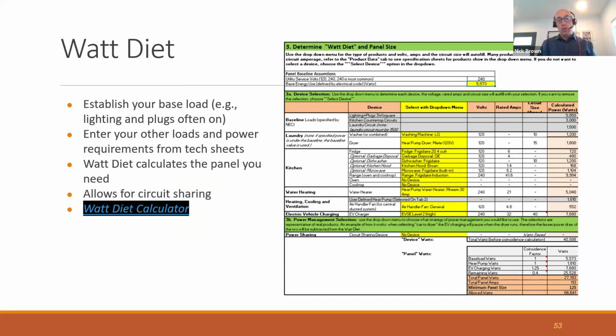Watt Diet's a useful tool in this sense. It is a spreadsheet application available through the link, and we're going to send out the slides at the end of this through Sarah. It establishes your base load, lighting, plug load, kitchen, laundry circuits. You enter your other loads, and the power requirements from those systems and what that calculates the size panel you need.